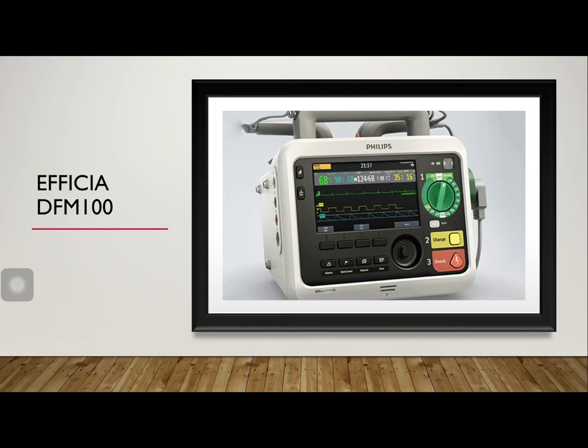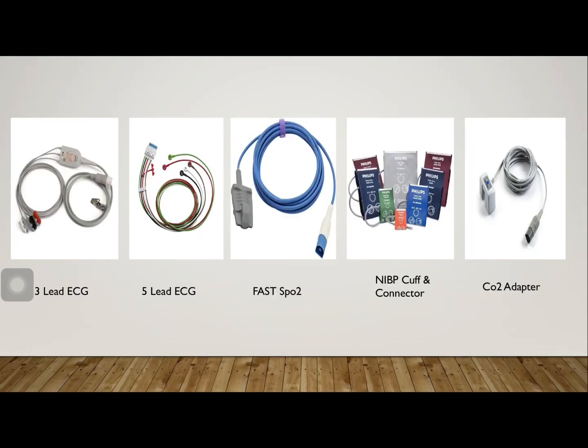Our defibrillator, the brand is Philips and the model is Efficia DFM100. For our accessories, we have our standard 3-lead ECG, our optional 5-lead ECG, and standard fast SpO2. Philips calls this fast SpO2 because it is anti-motion, shockproof, waterproof, and can still measure even in low perfusion. We also have an optional NIBP cuff and connector and an optional CO2 adapter. For our basic defibrillator, we only have the standard 3-lead ECG and fast SpO2.